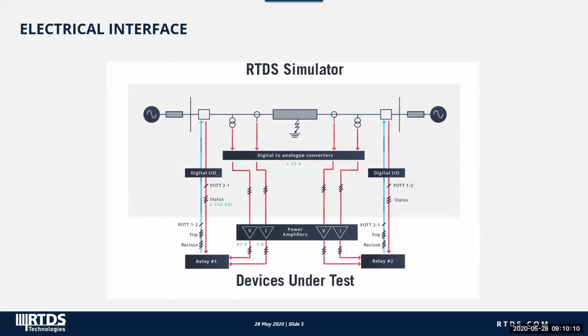In RTDS, we provide two solutions in terms of the interface between the simulated power system and the device under test. One is referred to as the electrical interface, and the other one is the IEC 61850 interface. As a simple example shown here, we have the power system simulated in the RTDS, in this gray box. Two protective relays are used to protect the breaker at each end of the line.